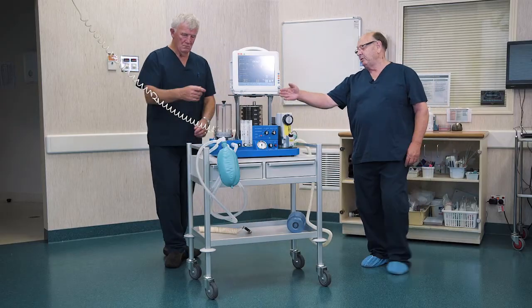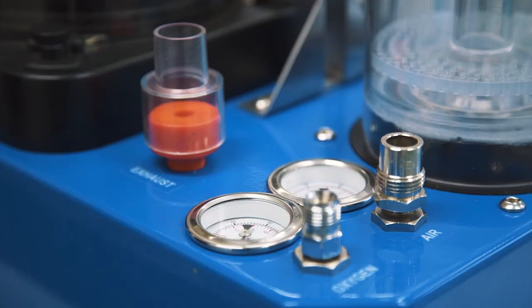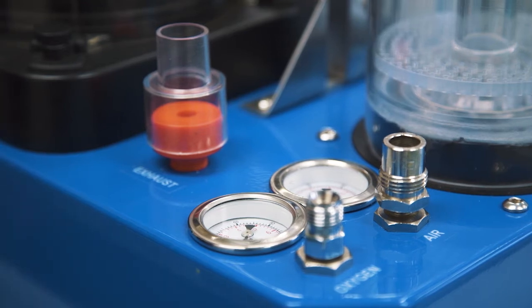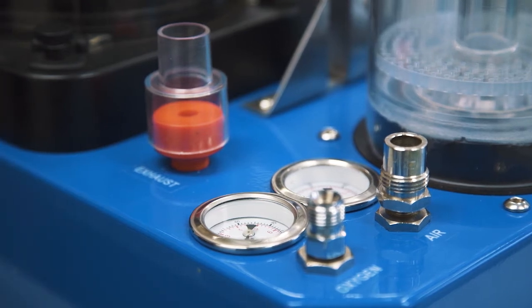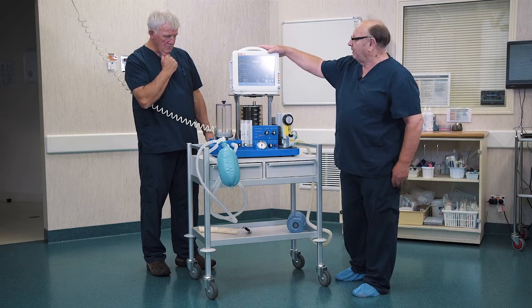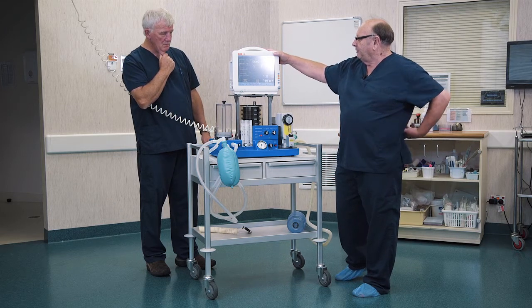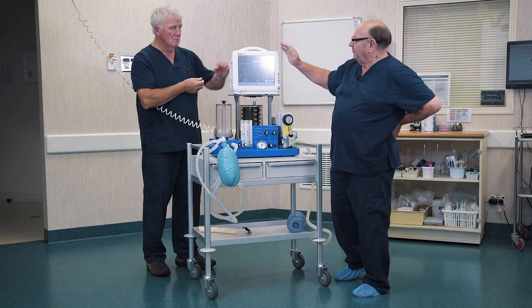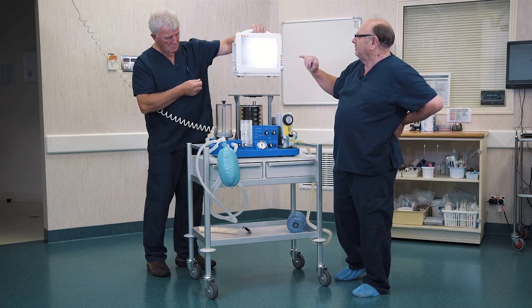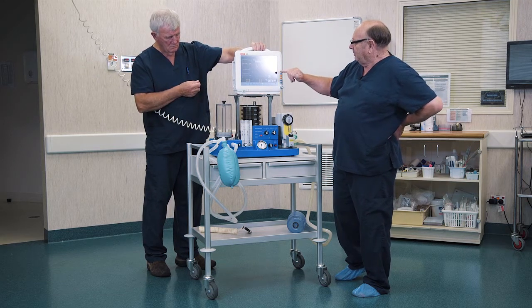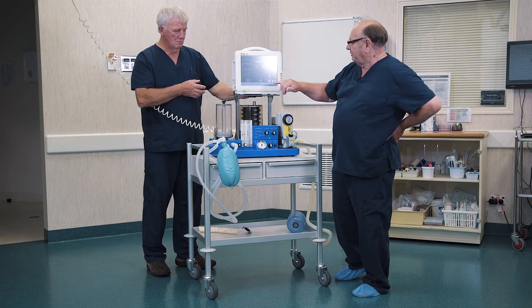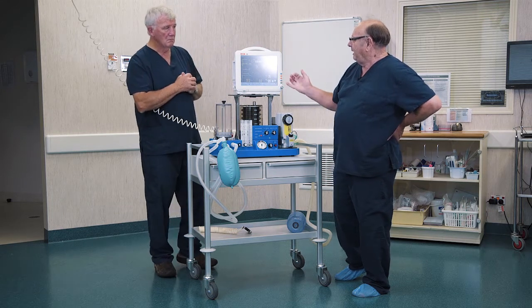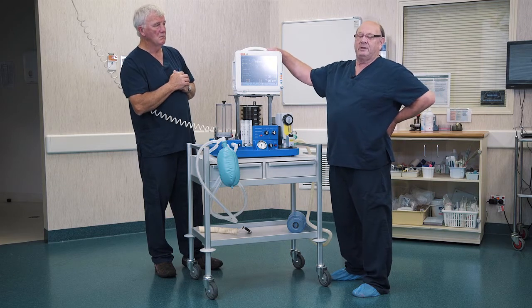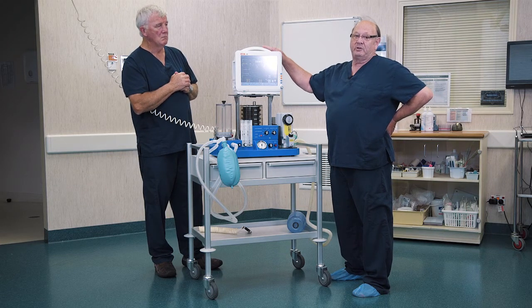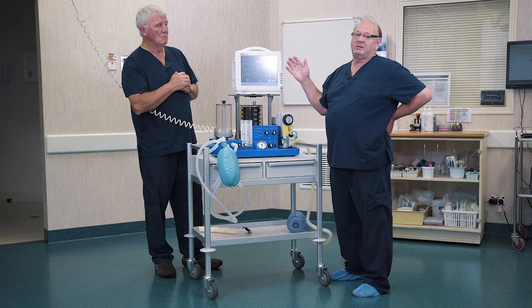Also around the back of the machine we have the exhaust for anaesthetic gases, which can be hooked to a passive or an active scavenging system. We also have a shelf here for a multi-parameter monitor which can give you your ECG, SpO2, invasive blood pressure, non-invasive blood pressure, temperature, and it also comes with a Phasein gas bench, Swedish designed. So you can have a multi-gas analysis on this machine as well.